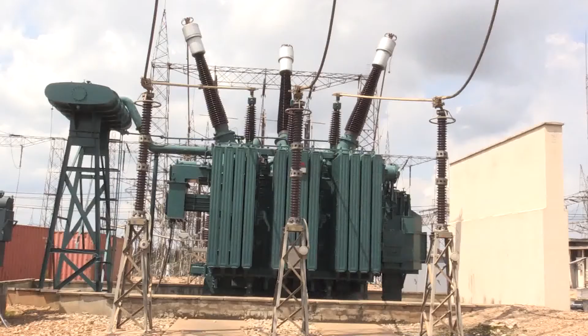What major projects have TCN engineers executed in this region? The one we did recently is the Kubwa installation of 1 by 60 MVA to replace the faulty one at Kubwa. We also did some rehabilitations which I can call major: there is one 60 MVA transformer at Ajaokuta Mains which has been out for long. It has been rehabilitated, its 330 kV circuit breaker has been replaced, and associated equipment, the switch gears, are rehabilitated.